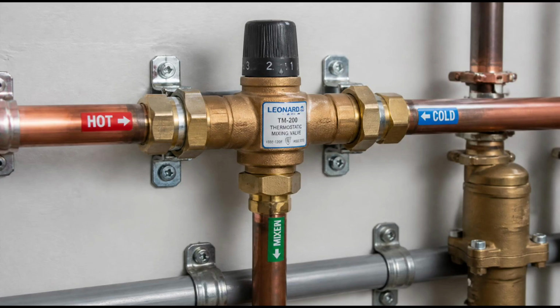That last concern, the risk of scalding, is managed at the fixtures themselves through mixing valves. A thermostatic mixing valve blends hot and cold water in precise proportions to deliver a consistent, safe output temperature, regardless of fluctuations in either supply. Even if the hot water in the building's pipes is maintained at a higher temperature for safety reasons, the mixing valve ensures that what emerges from a faucet or shower head is tempered to a comfortable and safe level.